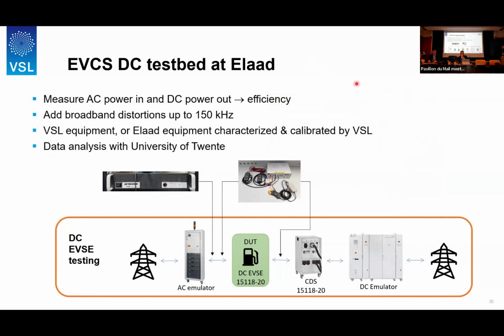So what do we want to do in this project? We want to measure the AC power in and the DC power out of the DC charging station. So we use our measurement system that I just showed before, connected here at the input of the EV charging system and also at the output. At the same time, we might inject distortions at the input of the charging station, and then see what is the effect on the metering, for instance. We can do that with our own setup, as I said, but we might also just use other commercially available equipment that will then be calibrated or characterized by us in our laboratory. And the data analysis will be done by the University of Twente, the group of Professor Rietveld.